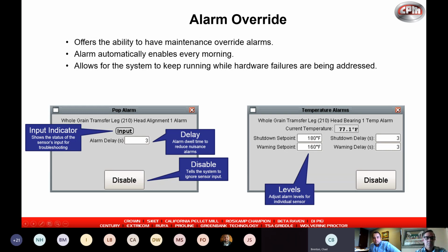With the maintenance level, you'll get one of these two pop-ups, depending on whether it's a digital or analog alarm. With the disable button, you can disable that alarm until a set time the next morning, so you can keep running that area or piece of equipment.